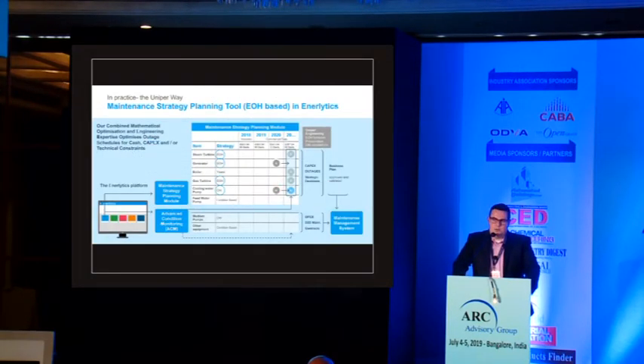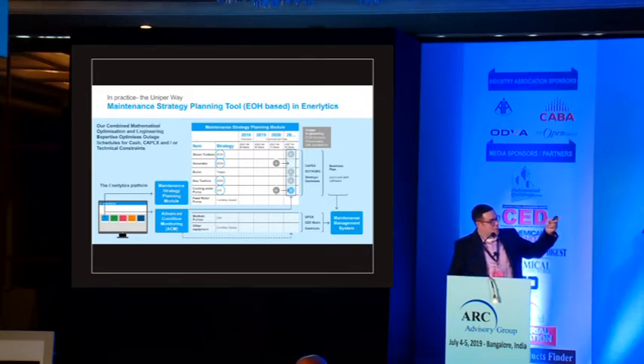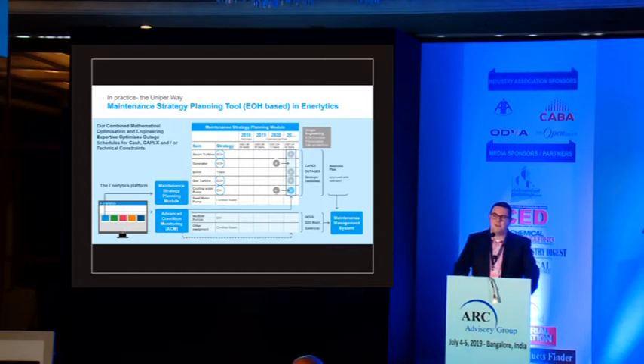Using all of these tools, we're able to start looking at the maintenance strategy around our units, to make them available when the money is available. So we now look at all the individual components and apply the right strategy for each. Whereas we would normally operate a time-based maintenance strategy on our steam turbine, because we're operating flexibly we're able to apply the EOH concept, equivalent operating hours, traditionally seen in gas, and move that across to here.